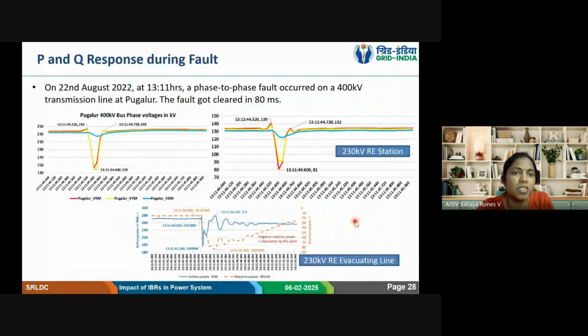This is also one such delayed recovery of P and Q. This also happened in Pugalur only. Here there was an RY fault in the station. During that time, we can see the P and Q responses are not in order. Whenever we observe these kinds of issues, we conduct a meeting with the concerned OEM and get to know why it didn't operate, why the inverters got tripped, why it didn't restart. Based on their reply, we suggest some corrections, and after taking the corrective actions, we have seen these trippings come down.